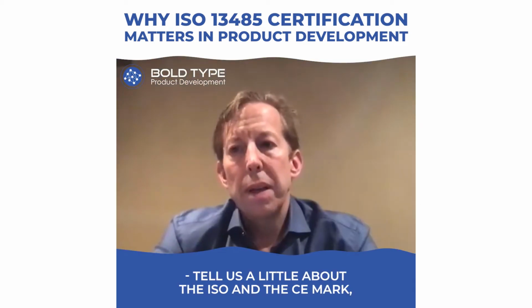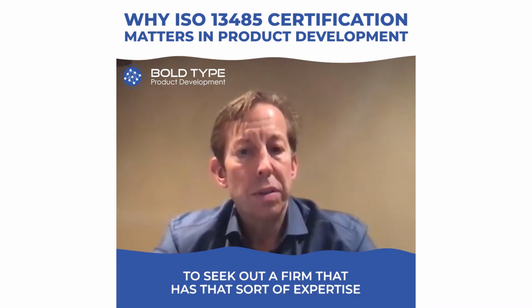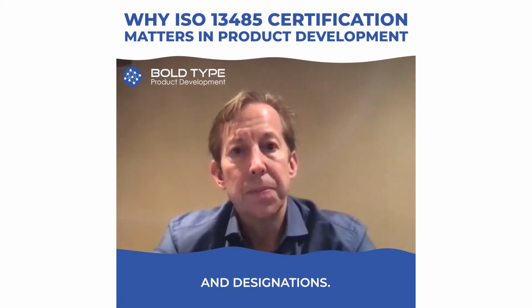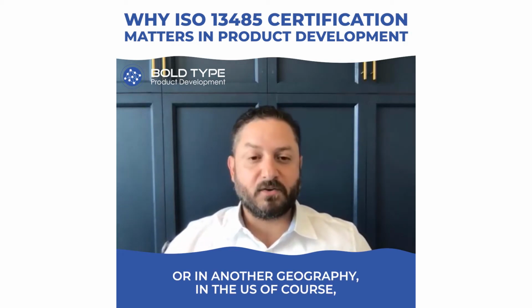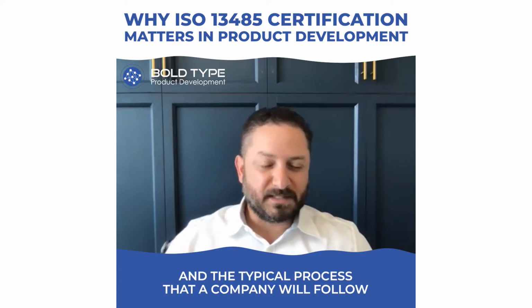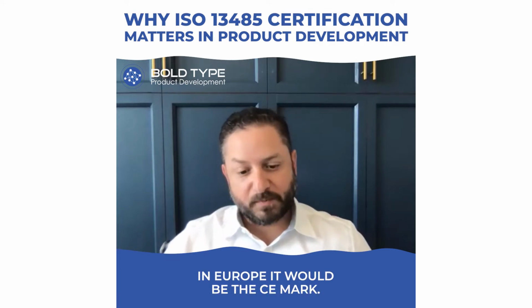Yeah, tell us a little about the ISO and the CE mark, why that's important, because some people may not know why it's important to seek out a firm that has that sort of expertise and designations. Sure. So whether you're trying to launch a product in the US or in Europe or in another geography, in the US, of course, that's regulated by the FDA. And the typical process that a company will follow is a 510(k), although sometimes they will follow a PMA. In Europe, it would be the CE mark.